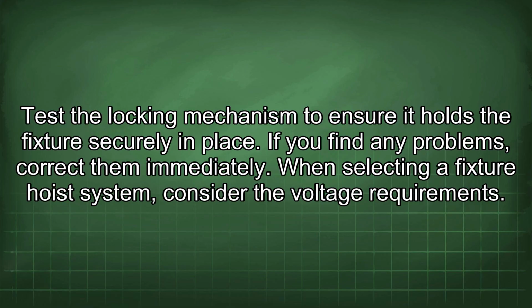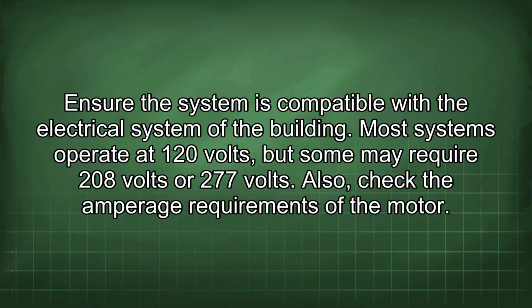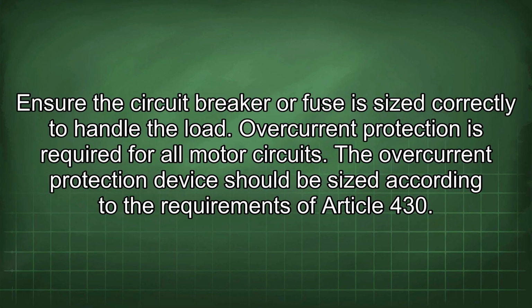When selecting a fixture hoist system, consider the voltage requirements. Ensure the system is compatible with the electrical system of the building. Most systems operate at 120 volts, but some may require 208 volts or 277 volts. Also, check the amperage requirements of the motor. Ensure the circuit breaker or fuse is sized correctly to handle the load. Overcurrent protection is required for all motor circuits.